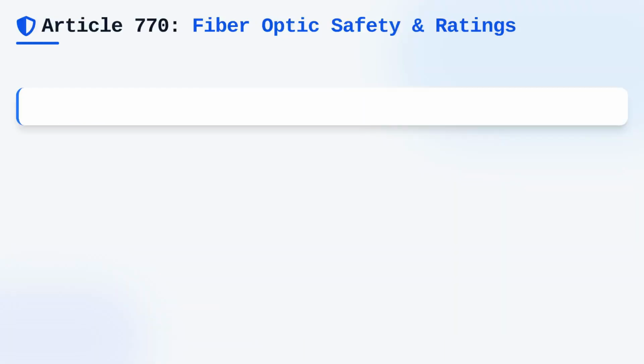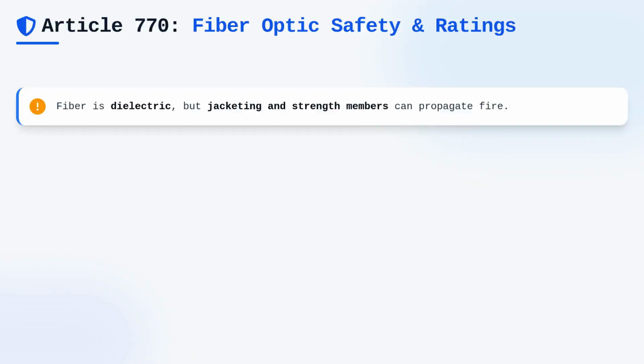When we examine Article 770 regarding optical fiber cables and raceways, we see a distinct focus on the physical properties of the medium itself. While fiber is dielectric, the cables themselves often contain strength members and jacketing materials that can contribute to fire spread if not properly rated. This is where the hierarchy of flammability ratings becomes critical to our design decisions.